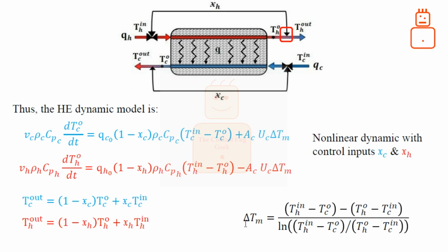This dynamic is fully nonlinear. The nonlinearity comes from two sources. The first is the logarithmic mean of the temperature difference we saw earlier, and the second is the direct multiplication between the control action—the fraction of the bypass valve—and the state. So there is a direct multiplication between the control action and the state, and the state also appears in a fully nonlinear relationship in the delta Tm.